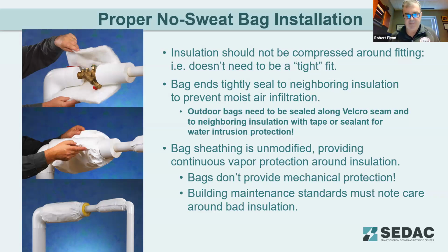Insulation should not be compressed, as Sean stated earlier. Bags tightly sealed to the neighboring insulation to prevent moist air infiltration. Outside bags need to be sealed with a Velcro seam to the neighboring insulation with the tape and sealant for water intrusion protection. Bags sheathing is unmodified, providing continuous vapor protection around insulation. Bags don't provide mechanical insulation protection. It's the insulation inside that actually does the protection.